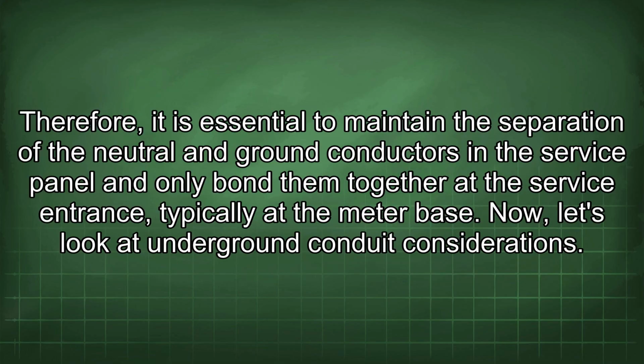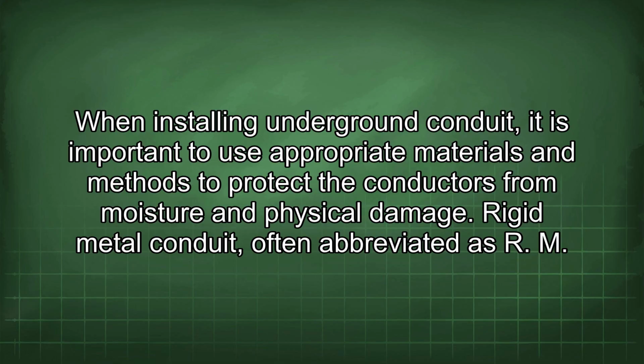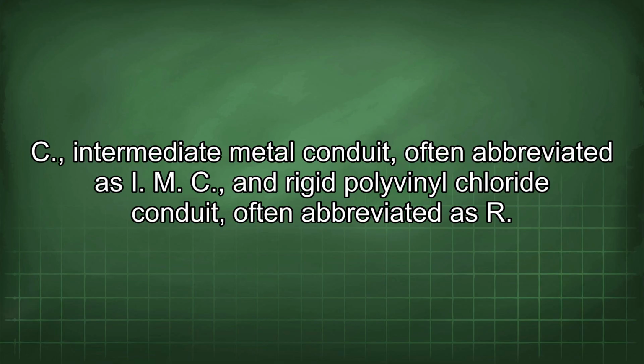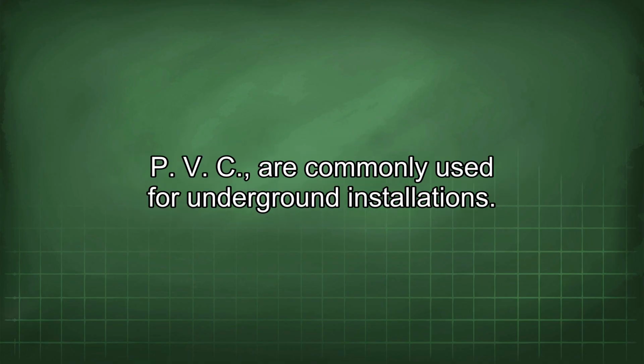Therefore, it is essential to maintain the separation of the neutral and ground conductors in the service panel and only bond them together at the service entrance, typically at the meter base. Now, let's look at underground conduit considerations. When installing underground conduit, it is important to use appropriate materials and methods to protect the conductors from moisture and physical damage. Rigid metal conduit, often abbreviated as RMC, intermediate metal conduit, often abbreviated as IMC, and rigid polyvinyl chloride conduit, often abbreviated as RPVC, are commonly used for underground installations.